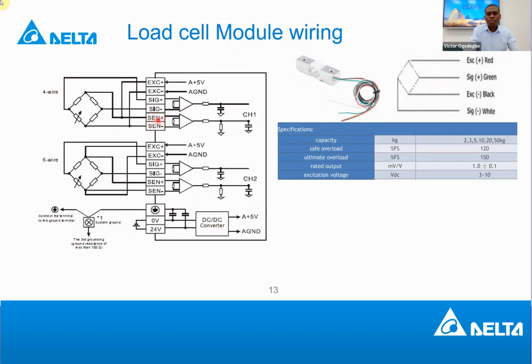So in case you have the sensor installed at a very far distance, if this is connected, it will ensure that what is being read from the sensor is correct. It will help to balance the impedance so that there's no interference and no error in the reading. So you connect this also to the excitation voltage. For the 4 cables, you do the same.